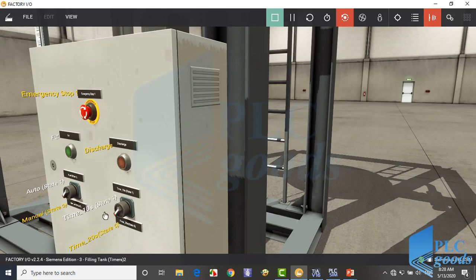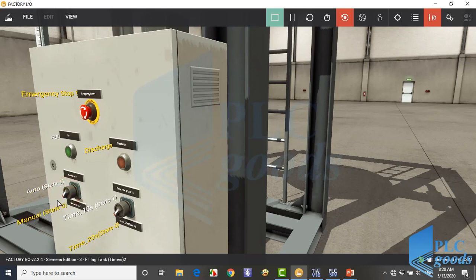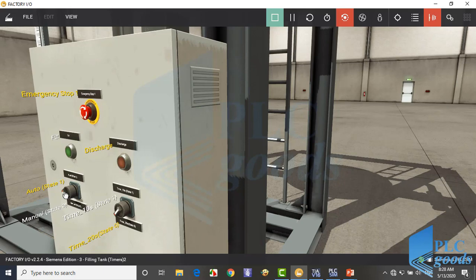Next, here we have two selectors. This is auto manual selection. In the manual mode, every valve will be on until its push button is pressed. In the auto mode, when a push button is pressed, the related valve will be on for a specified time 10 or 20 seconds, which can be chosen by next selector.